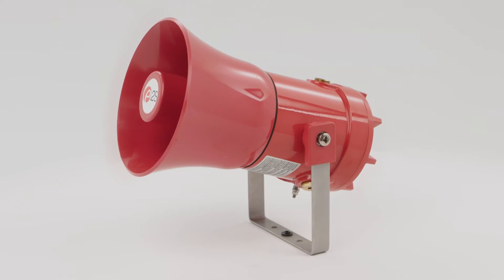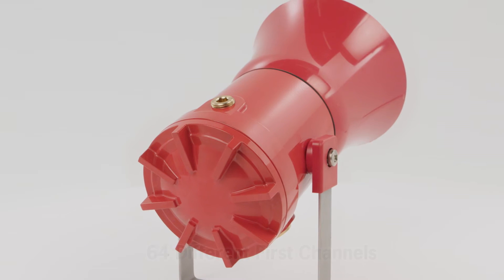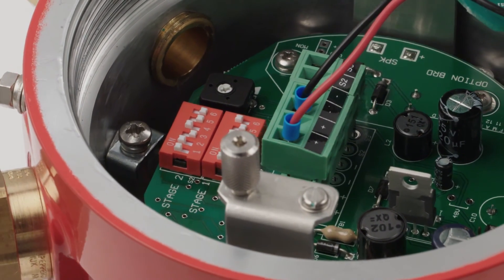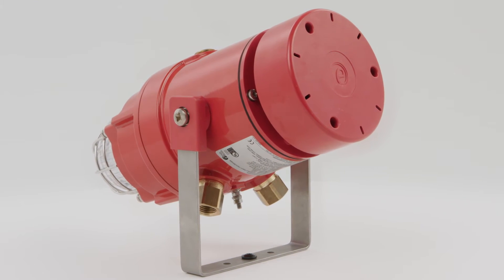The D1X alarm horns offer 64 different first channel or stage alarm sounds, up to 125 dBA. Each stage can be remotely triggered to a 2nd, 3rd and 4th channel alarm sound, signalling multiple warnings from just one device.